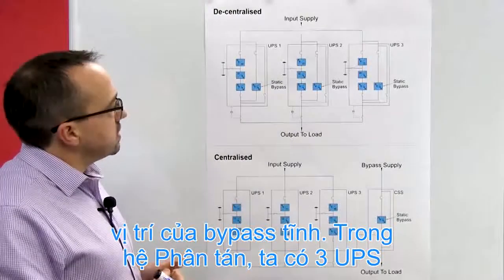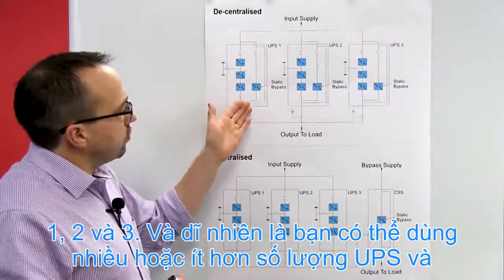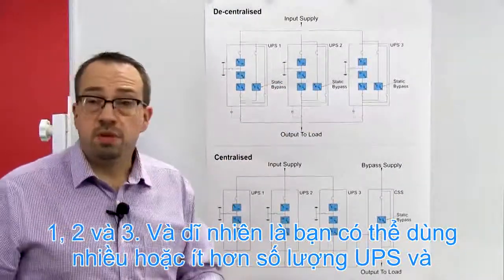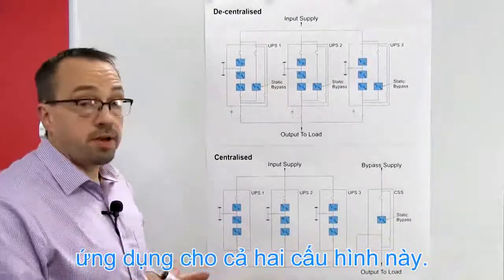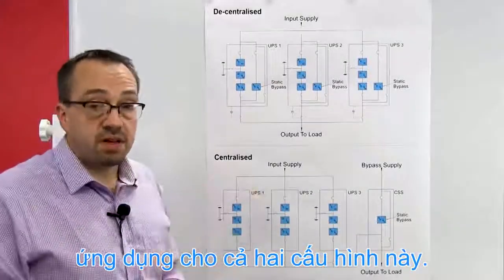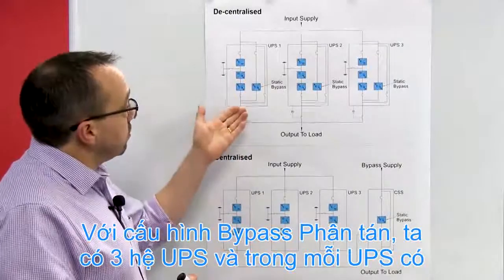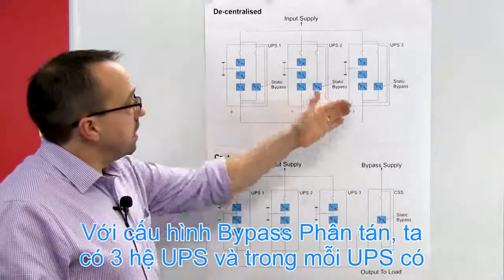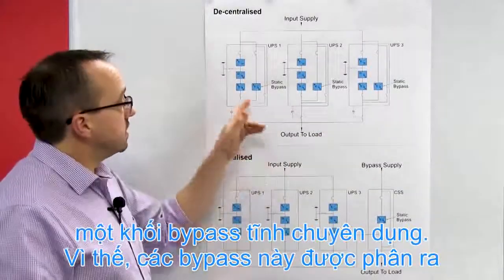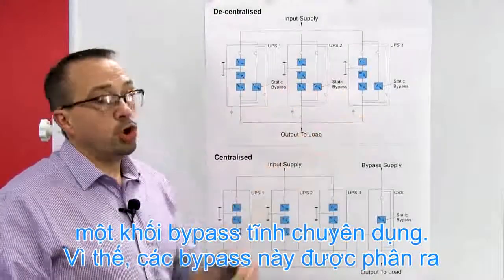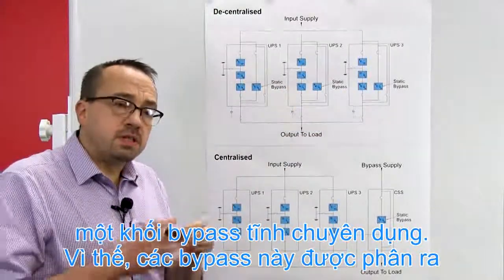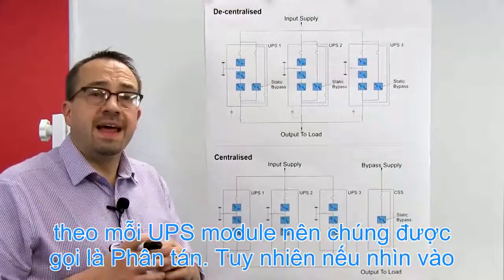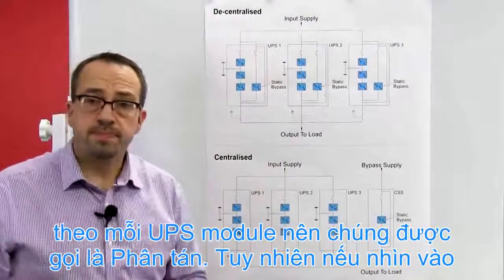In the decentralized system we have three UPSs, 1, 2 and 3. Now obviously you can use either more or fewer UPS systems, and that applies to both the decentralized and the centralized. In the decentralized system we have three UPS systems, and inside each of the UPS there is a dedicated static bypass per UPS, and therefore the bypasses are split across the UPS modules and hence they are decentralized.